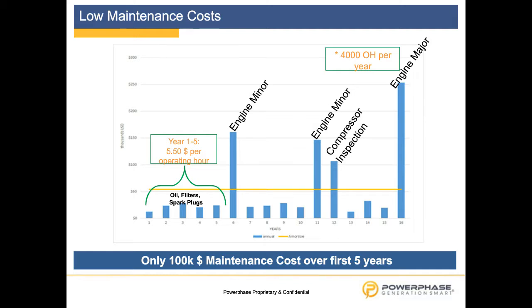The compressor will have its inspection and maintenance at around 48,000 hours, and we are flexible here, hiding, I would say, behind the plant maintenance, so there is no shutdown other than what you already planned for your gas turbines.